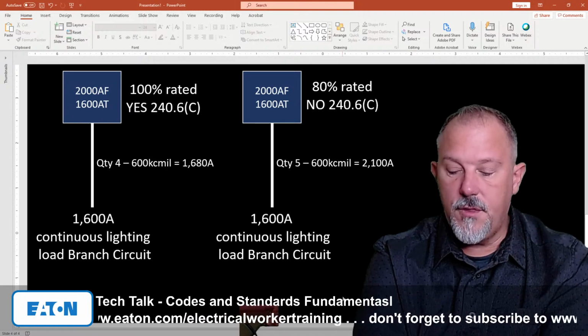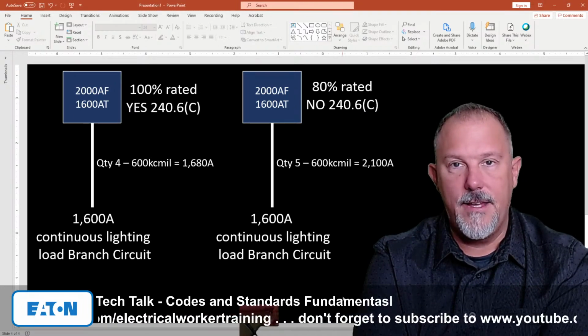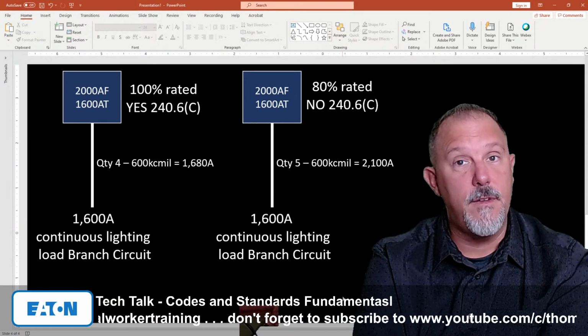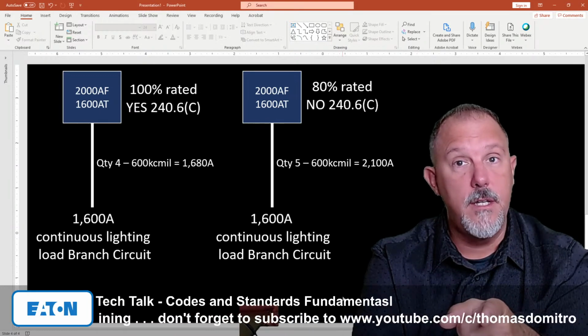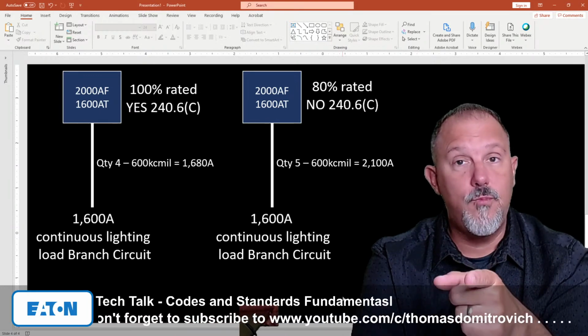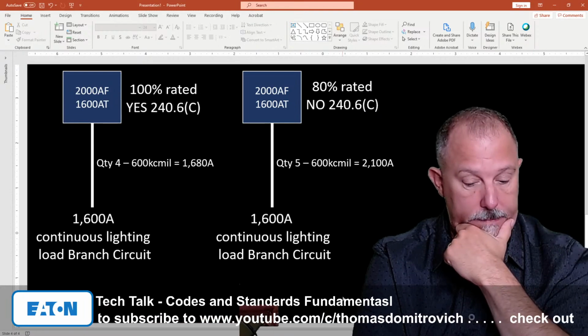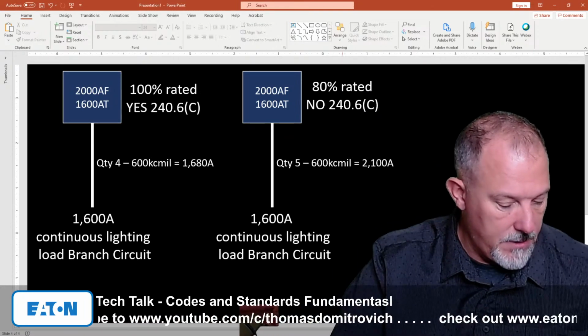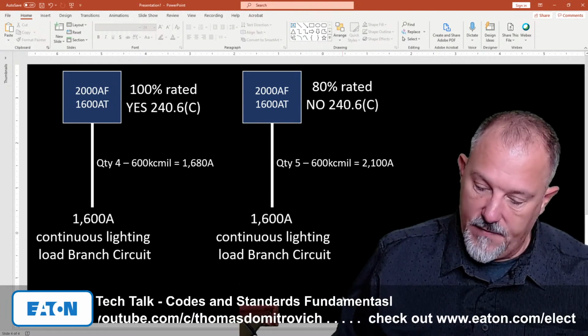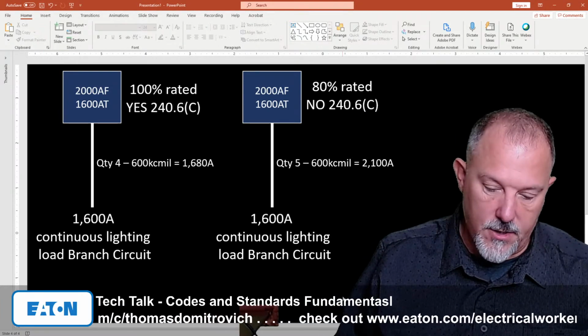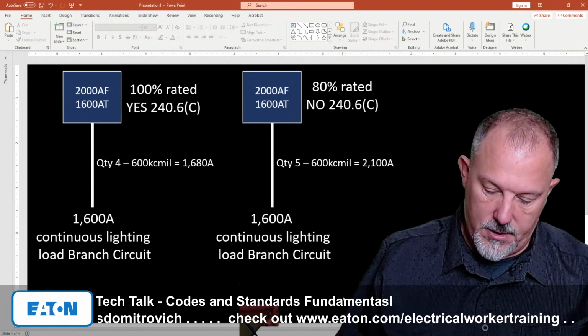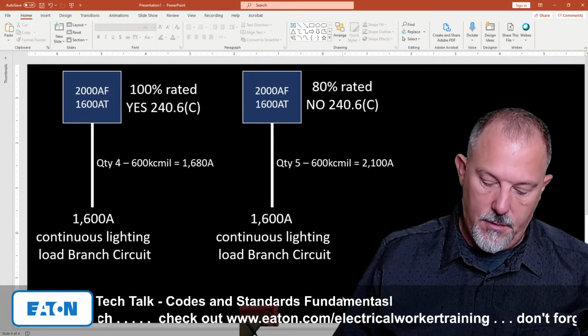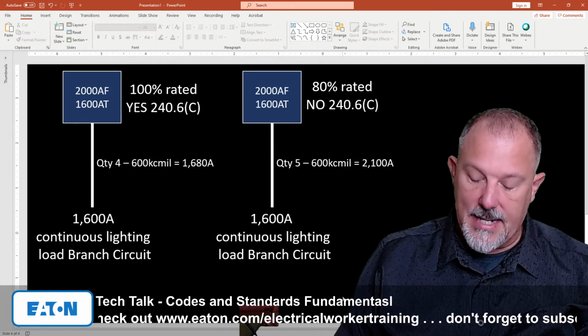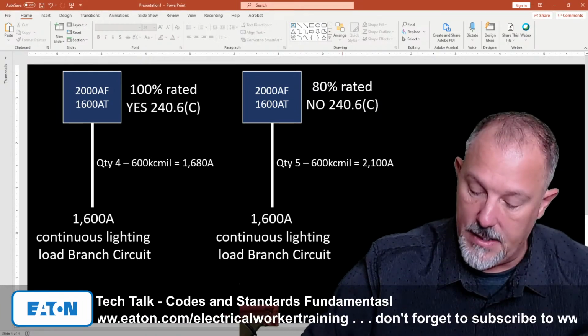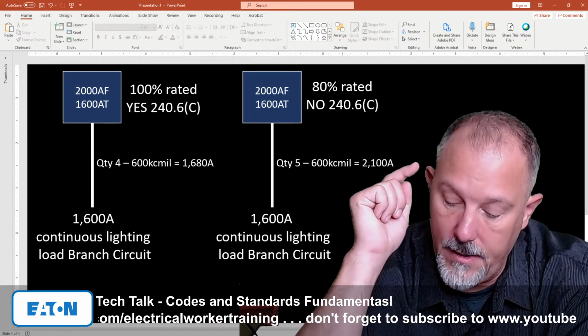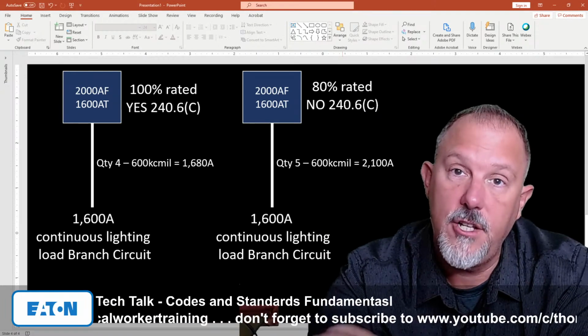There's nothing in 230.90a that mentions the 1.25 like we had in 215.3 and in 210.20a. And if I look at the service conductor, where's the service entrance conductors, is in 230.42, minimum size and ampacity. I do have exactly the same as what you have in 210 and 215.